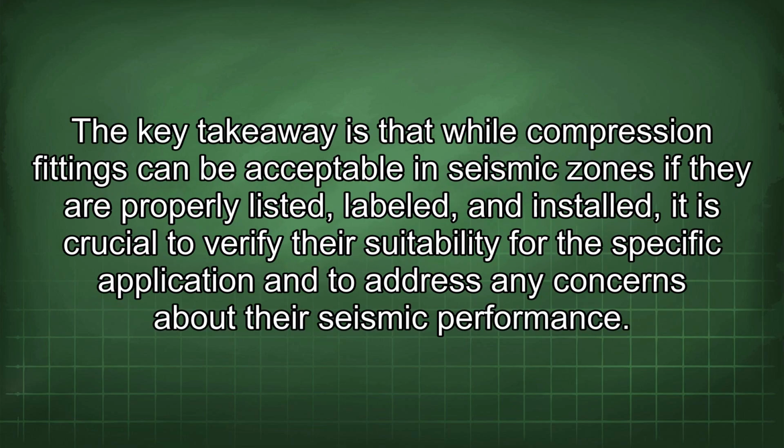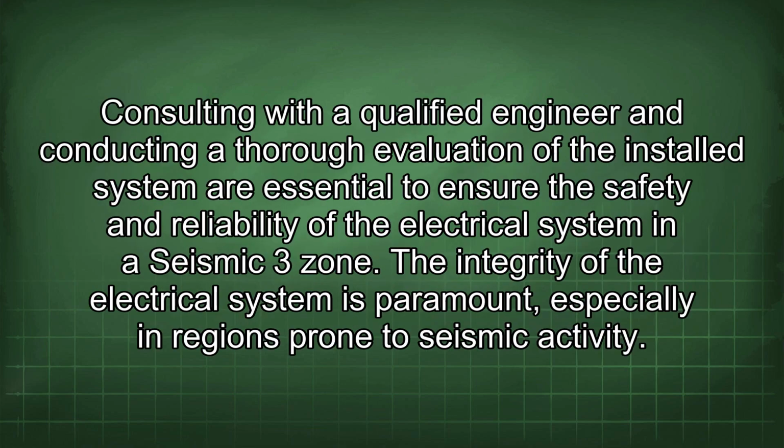The key takeaway is that while compression fittings can be acceptable in seismic zones if they are properly listed, labeled, and installed, it is crucial to verify their suitability for the specific application and to address any concerns about their seismic performance. Consulting with a qualified engineer and conducting a thorough evaluation of the installed system are essential to ensure the safety and reliability of the electrical system in a seismic zone.